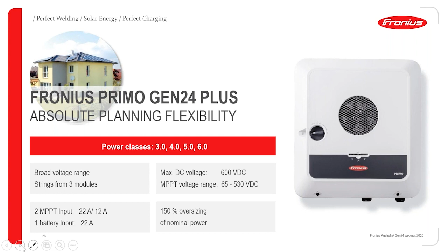The number of PV inputs also is 2, compared to our current Symo, which is 1. Here you will have 22 amps on the first tracker and 12 amps on the second tracker. What this means is, for example, you can put nearly 100% on one tracker, or if you want, you can do 50-50. So there are quite flexible options in terms of PV input. Then you also have one battery input, 22 amps, for charging from the inverter, and that's how we achieve this goal of high power from the panels to the battery. Those inverters will be able to oversize by 150%. That's also something to keep in mind.